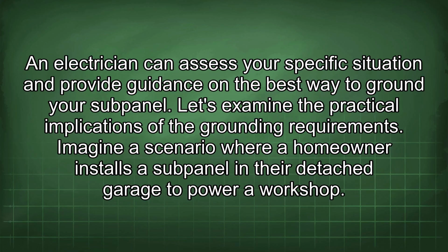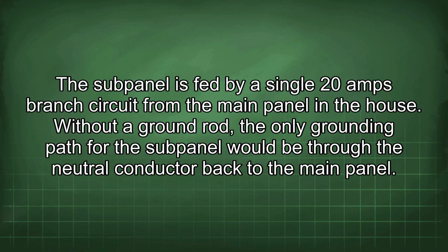Let's examine the practical implications of the grounding requirements. Imagine a scenario where a homeowner installs a subpanel in their detached garage to power a workshop. The subpanel is fed by a single 20 amp branch circuit from the main panel in the house.